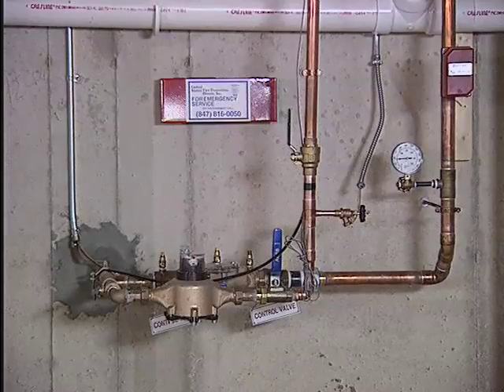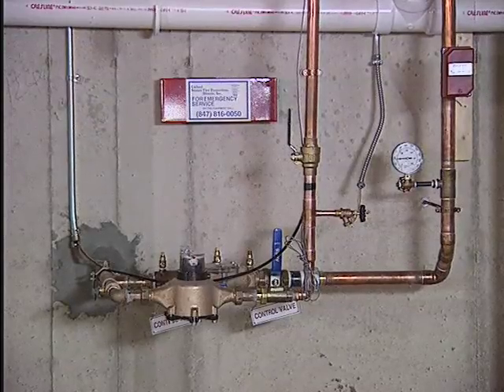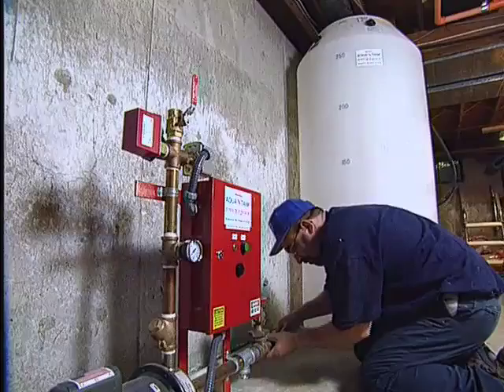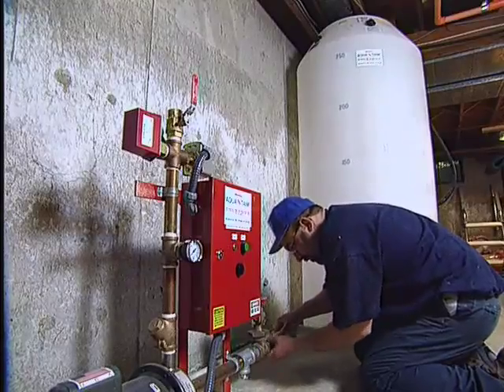We're in a two-story house with a full basement in the Midwest. Now, in this case, the water source is the municipal water supply. That means the 10-minute duration required by NFPA 13D really shouldn't be a problem. The water will always be available when it's needed and should never run out. Now, if you're not on a municipal water supply, for example, if you have a well or your water pressure is very low, then you'll need a tank and a pump to provide that pressure.